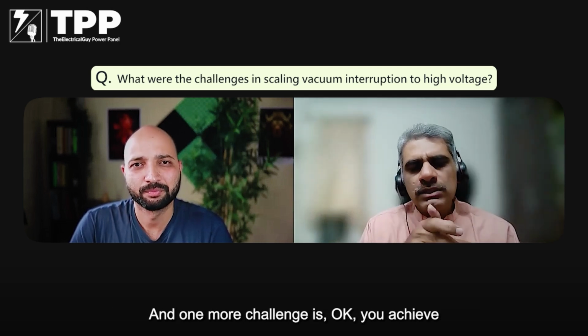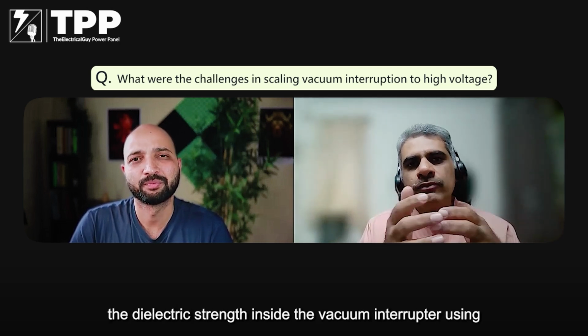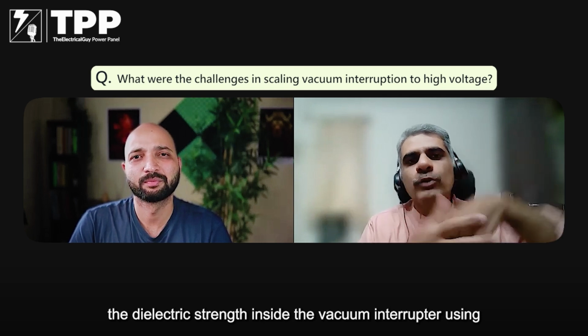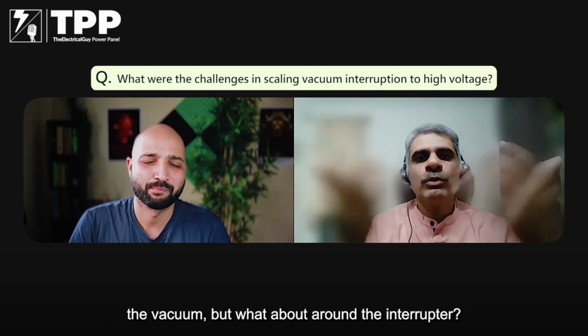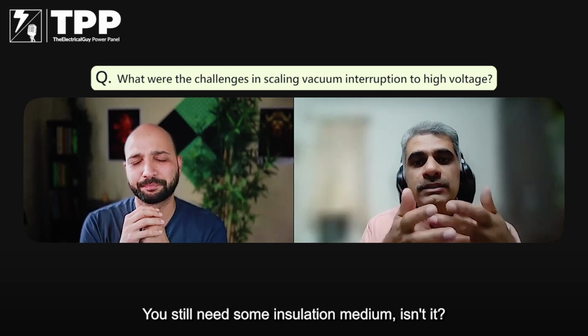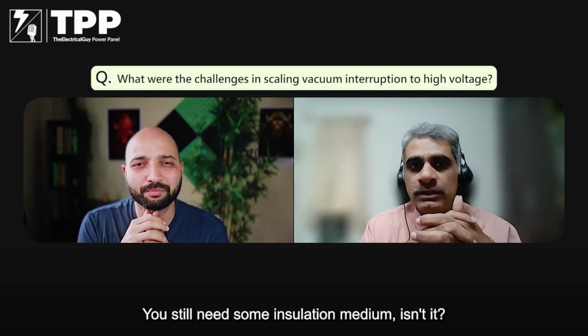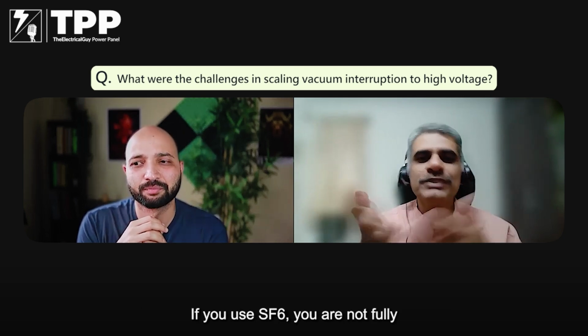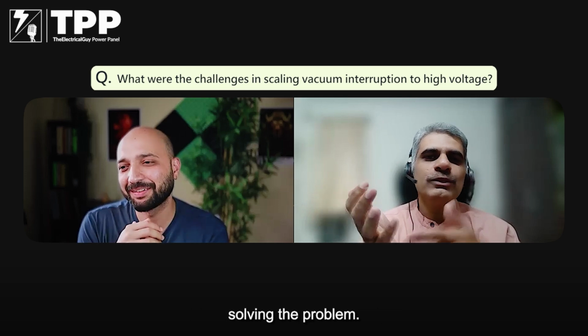And one more challenge is, okay, you achieve the dielectric strength inside the vacuum interrupter using the vacuum, but what about around the interrupter? You still need some insulation medium, isn't it? You cannot use SF6. If you use SF6, you are not fully solving the problem.